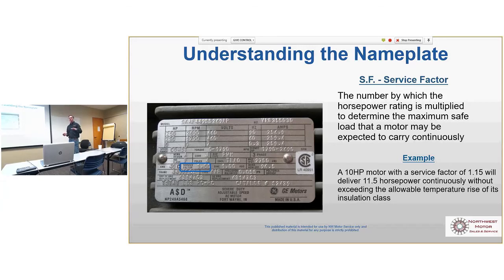So just keep in mind, any motor on a drive is 1.0 service factor. You no longer have that headroom. You can't get 11.5 horse out of a 10 horse motor when it's on a drive. You're just going to get 10. Okay.